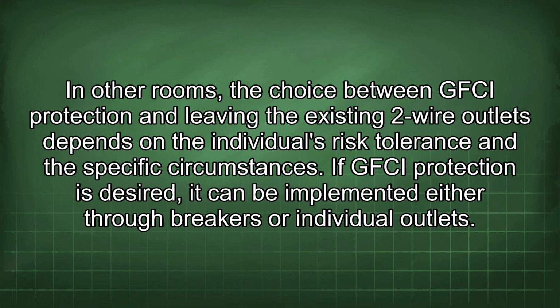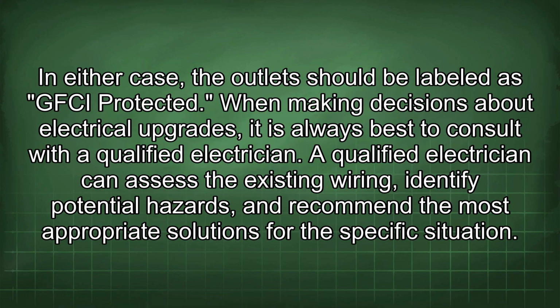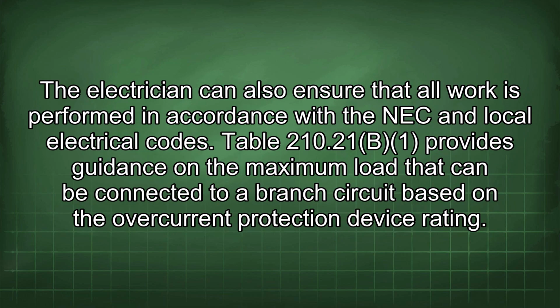In other rooms, the choice between GFCI protection and leaving the existing 2-wire outlets depends on the individual's risk tolerance and the specific circumstances. If GFCI protection is desired, it can be implemented either through breakers or individual outlets. In either case, the outlet should be labeled as GFCI protected. When making decisions about electrical upgrades, it is always best to consult with a qualified electrician. A qualified electrician can assess the existing wiring, identify potential hazards, and recommend the most appropriate solutions for the specific situation. The electrician can also ensure that all work is performed in accordance with the NEC and local electrical codes.